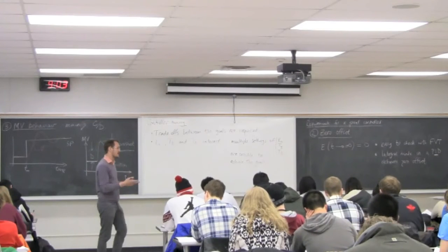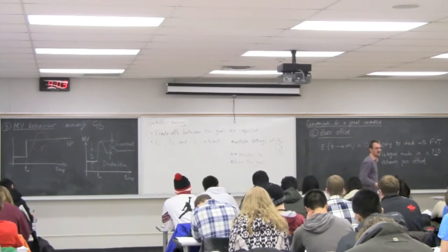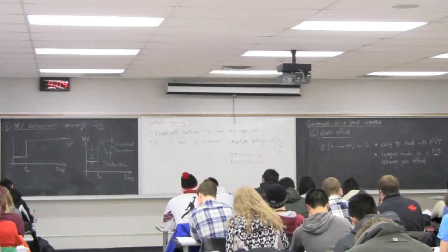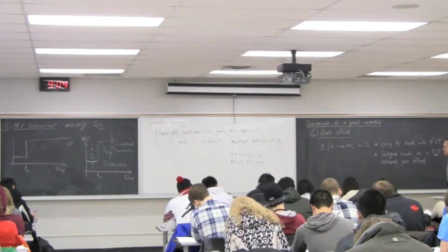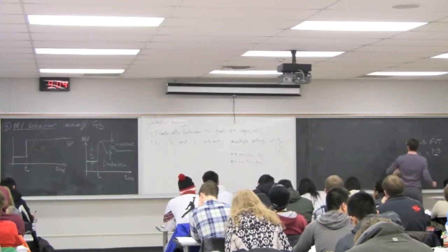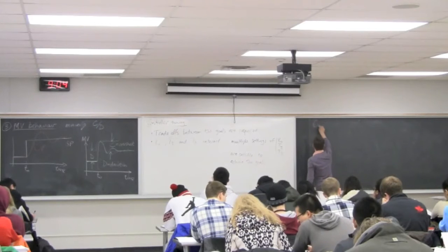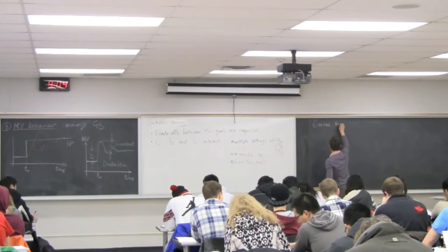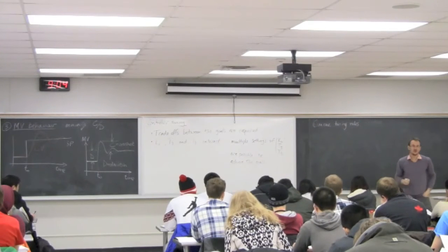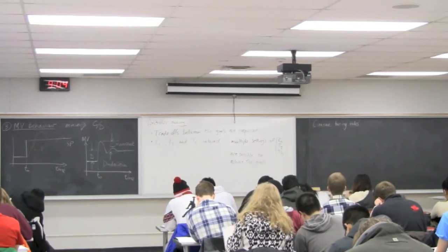KC, TI, and TD values to use. And what this handout in front of you is, is a study that was done by Dr. Marlin to find settings that work well in most situations. And that's our initial way we're going to consider tuning a controller. They're called the Ciancone tuning rules, and what they do is they achieve these goals well for most processes.